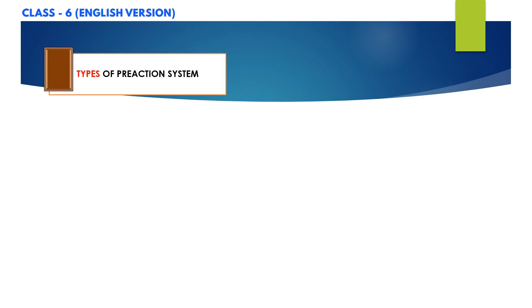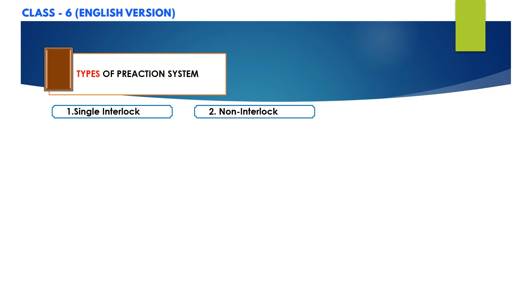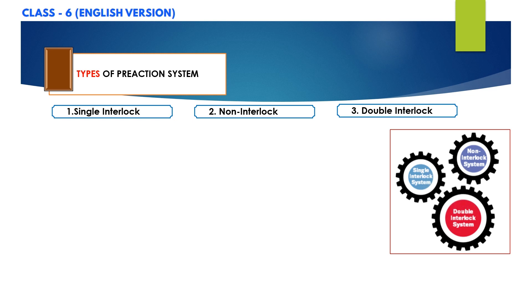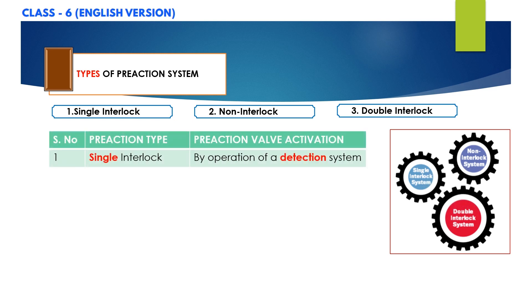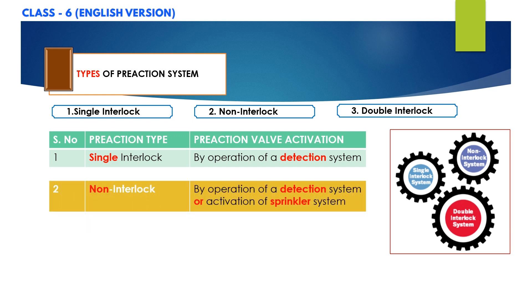NFPA 13 defines three basic types of pre-action systems: number one, single interlock type; number two, non-interlock type; and number three, double interlock type pre-action systems. Single interlock pre-action systems admit water to sprinkler piping upon operation of detection devices only, and detection systems may be electric or pneumatic. Non-interlock pre-action systems admit water to sprinkler piping upon either operation of detection devices or automatic sprinklers.